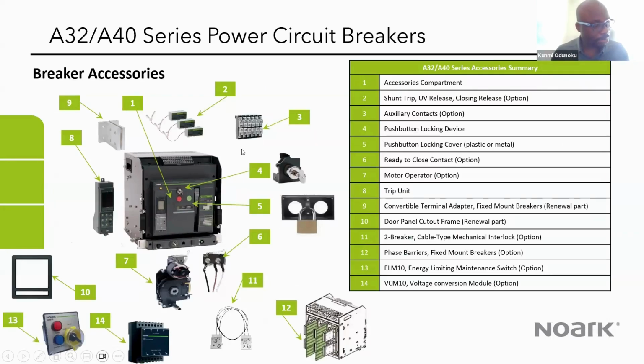Now to go into more details about the breaker itself, we have these accessories here. I'm just going to do a quick run through them. We have the accessories compartment, and inside there you can have different kinds of accessories. We have the shunt trip, the undervoltage release, and the closing release. The shunt trip helps you give a remote signal to open the breaker remotely, while the undervoltage is a protection. When the voltage in the system drops to a particular level, the undervoltage trips the breaker, and it will not allow the breaker to close while the undervoltage is still present in the system. The closing release helps you to remotely close the breaker.